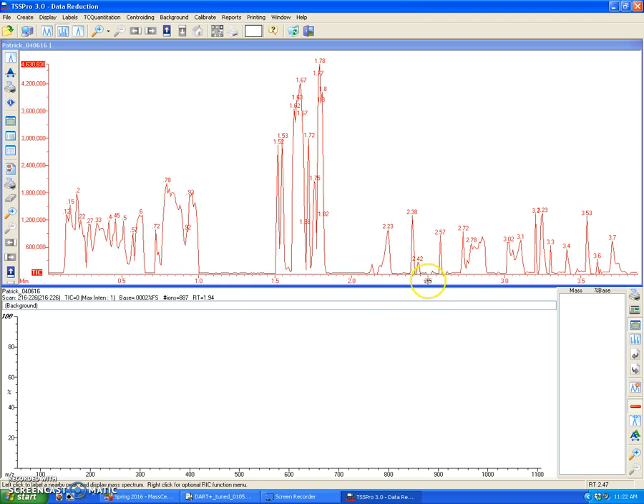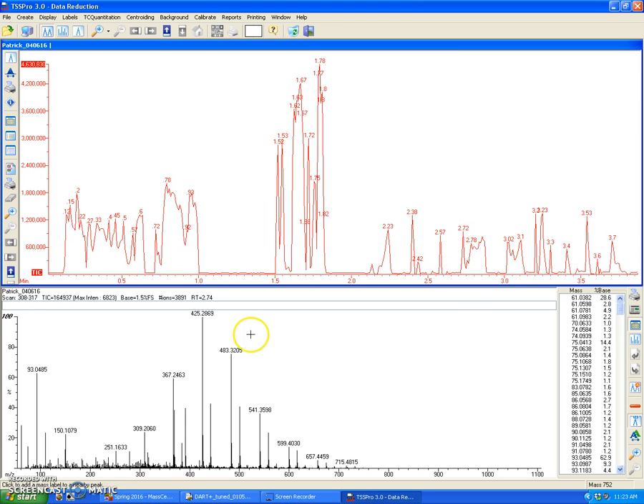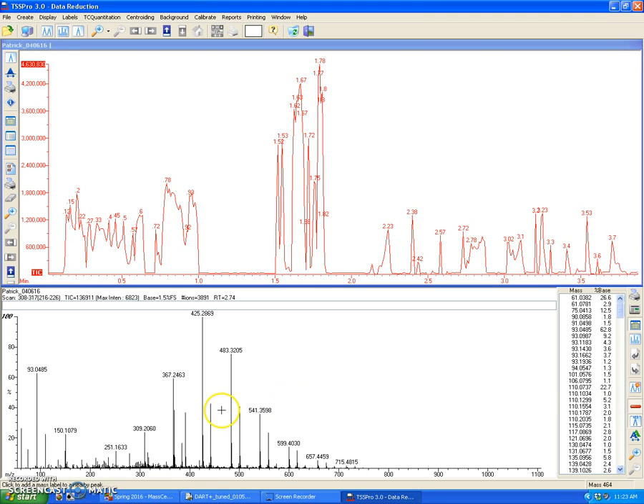To apply this to other regions of where I actually did an analysis, I can just average a region, and then click on this button right here, subtract MS background. And you can see that the mass spectrum has slightly shifted because it removed those background ions.